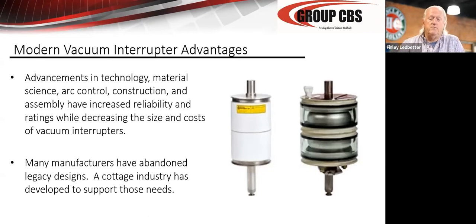Here you see a modern interrupter on the left, an older interrupter on the right, and you see the pinch tube on the top, and the interrupter is made out of leaded glass. The leaded glass is penetrated by small noble gases. The pinch tube can't be sealed very well. That's why it's got all that epoxy daubed on the top. I don't think I would trust that. So the pinch tube breakers have a pretty high leak rate.